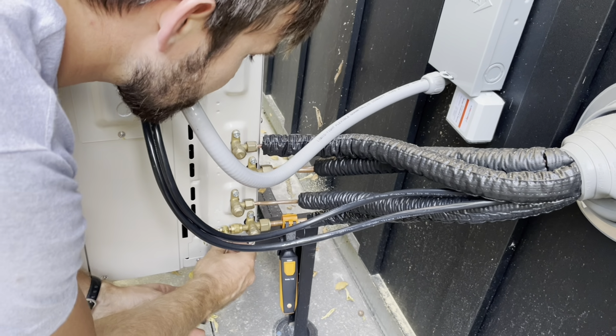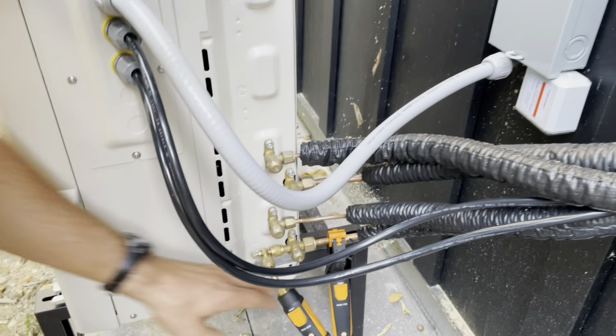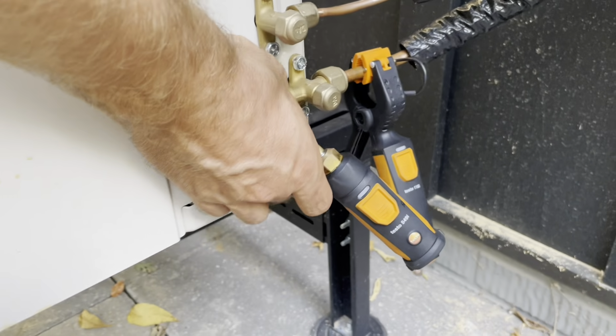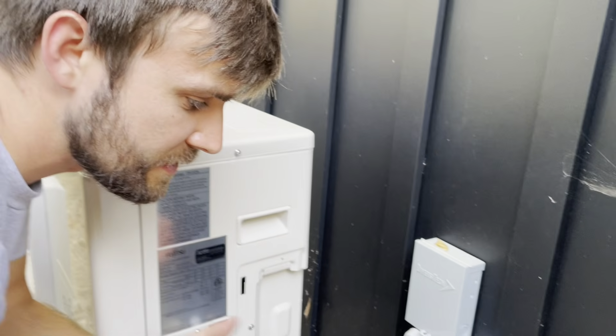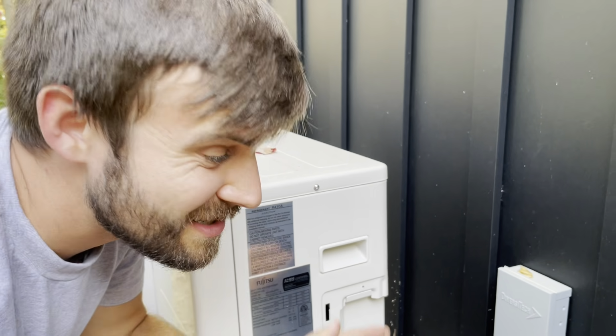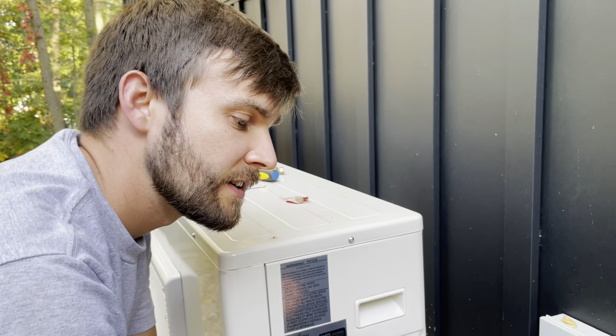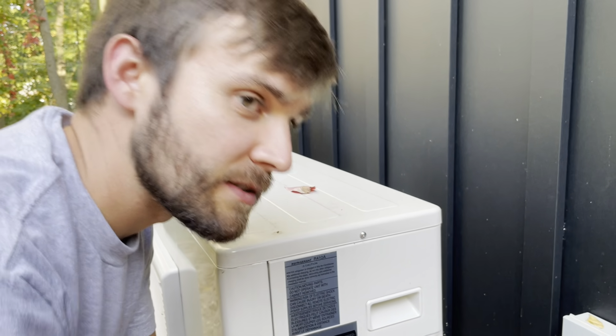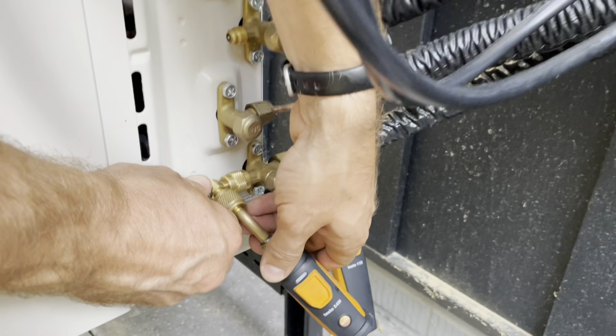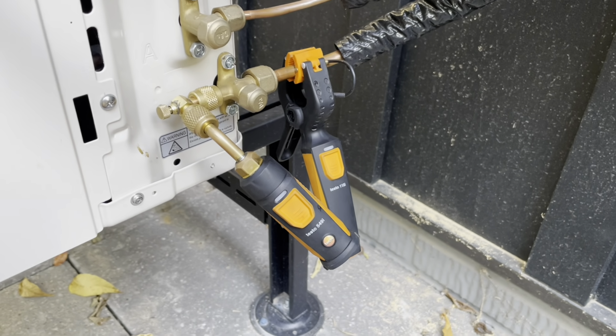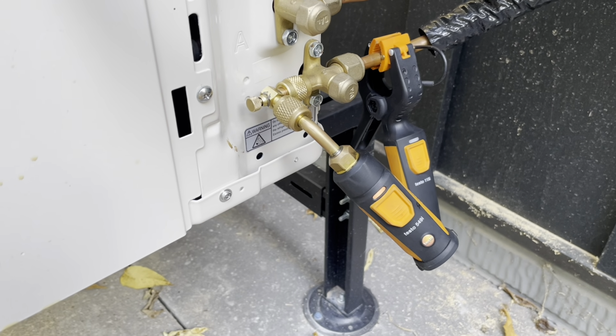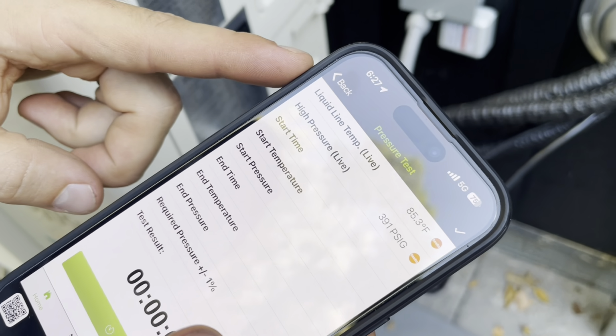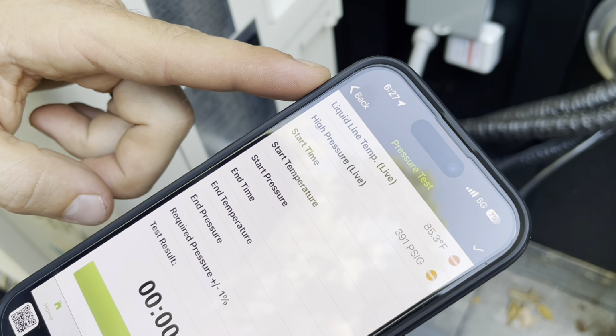Bad design choices, Fujitsu. So this is called a temperature compensated pressure test. So it takes into account the temperature of the line. So if that was to change, say if it changed 10 degrees, if it went down 10 degrees, the pressure would go down a little bit, and that would show up as a leak. But if you know the temperature went down, then you know it's not a leak. And it's all digital, so I know high pressure 391, temperature is 85 point.